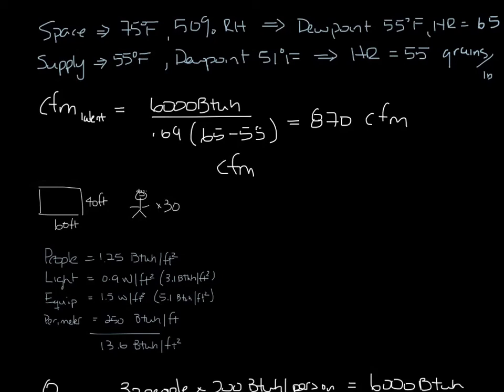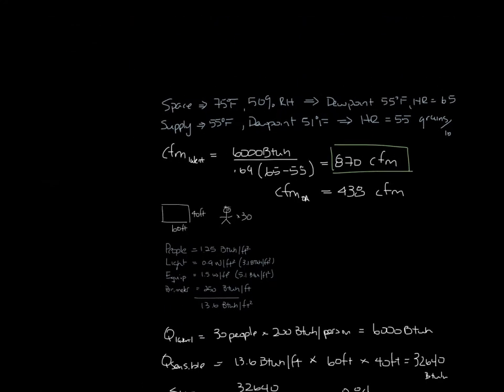We calculated earlier that the CFM needed for the outside air ventilation requirement is 438 CFM. So you can see from this, you need to supply 870 CFM to handle the latent load, which will also handle the ventilation requirement.